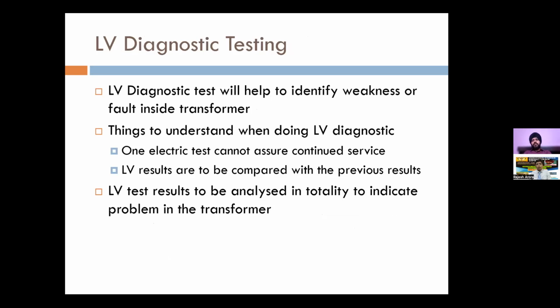Once you have ruled out all maloperations and you have identified that there is some particular issue with this transformer, now you need to take up the LV diagnostic testing. LV diagnostic tests will help to identify the weakness or the fault inside the transformer. An important thing to note is that there have been incidences where the LV diagnostic tests were all healthy, but still the transformer was damaged, particularly if we see a failure towards the neutral end. If there is any damage to a transformer or a reactor on the neutral side, winding resistance and all other test parameters can be healthy and still there is a fault inside. So a good LV diagnostic test does not mean that our transformer is healthy.